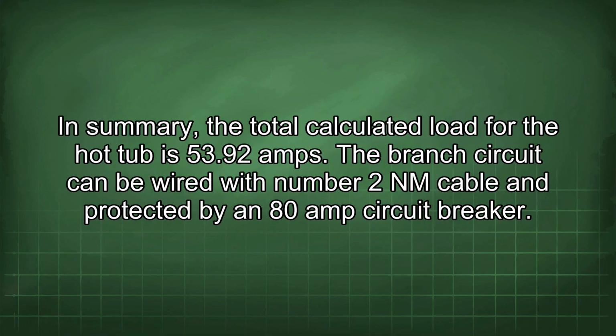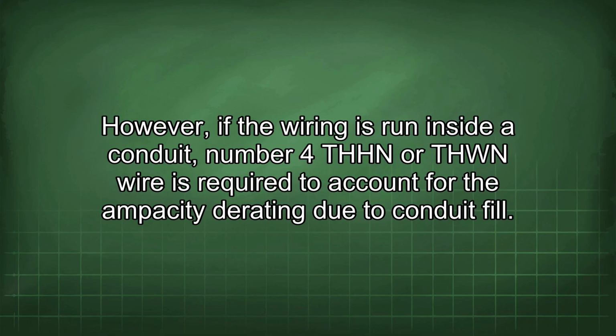In summary, the total calculated load for the hot tub is 53.92 amps. The branch circuit can be wired with number 2 NM cable and protected by an 80 amp circuit breaker. However, if the wiring is run inside a conduit, number 4 THHN or THWN wire is required to account for the ampacity derating due to conduit fill.